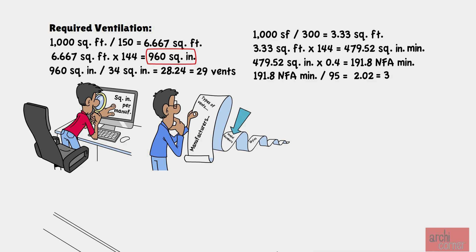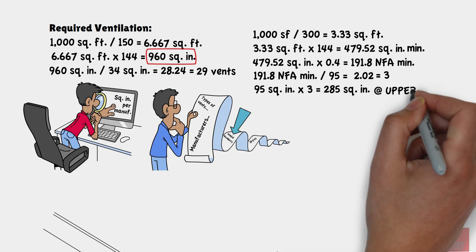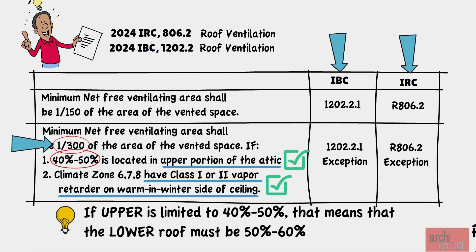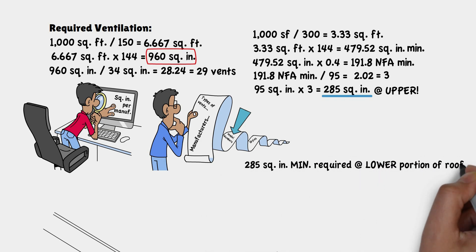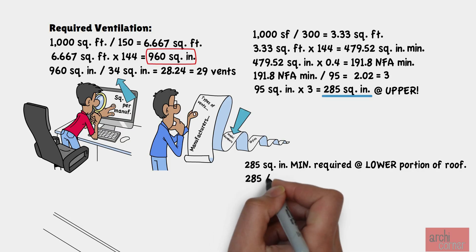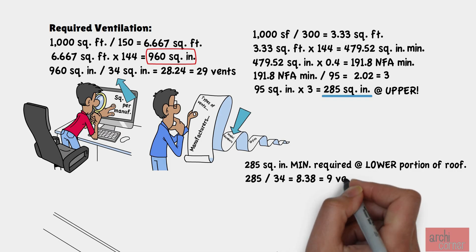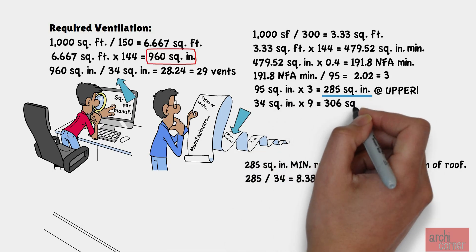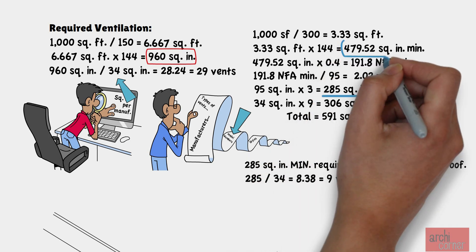Unfortunately, this will require three wind turbines. Three turbines times 95 square inches gives us 285 square inches of net free area from the turbines. We also need to get a minimum of 50% of airflow from the lower portion of the roof, so we must provide at least 285 square inches with eave vents. Dividing 285 by 34 equals 8.38, requiring 9 eave vents. Nine vents times 34 square inches equals 306 square inches of venting from under-eave vents, for a total of 591 square inches.